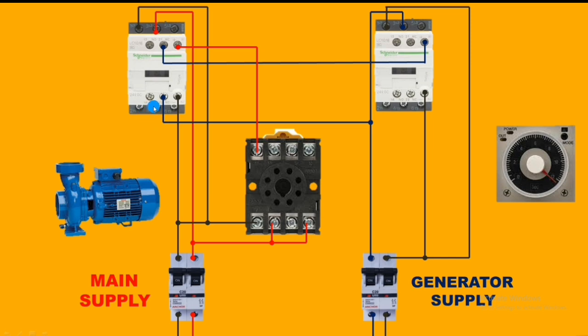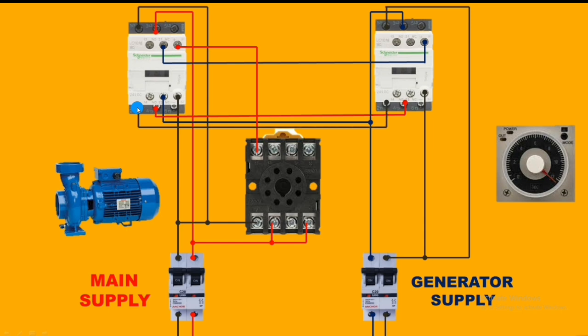The outputs of both contactors are looped together. First, loop L2 to L2 for the line loop, and second, loop L1 to L1 for the neutral loop. Whether the main contactor or the generator contactor is running, the supply will come to the house load. So we loop both line and neutral from the contactors and connect them — neutral to house load and line to house load.